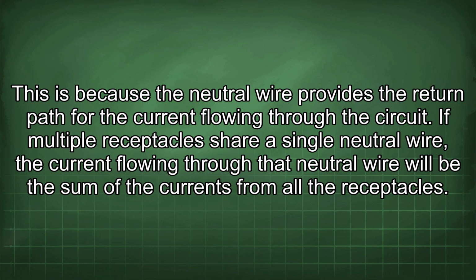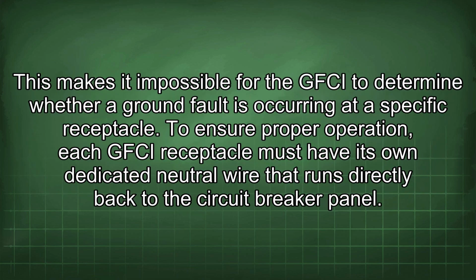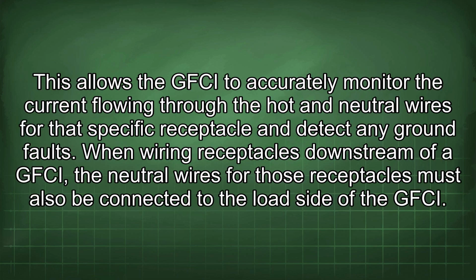If multiple receptacles share a single neutral wire, the current flowing through that neutral wire will be the sum of the currents from all the receptacles. This makes it impossible for the GFCI to determine whether a ground fault is occurring at a specific receptacle. To ensure proper operation, each GFCI receptacle must have its own dedicated neutral wire that runs directly back to the circuit breaker panel. This allows the GFCI to accurately monitor the current flowing through the hot and neutral wires for that specific receptacle and detect any ground faults.